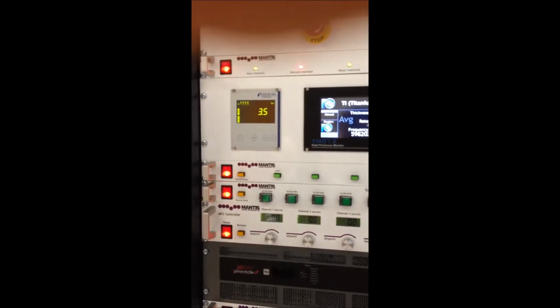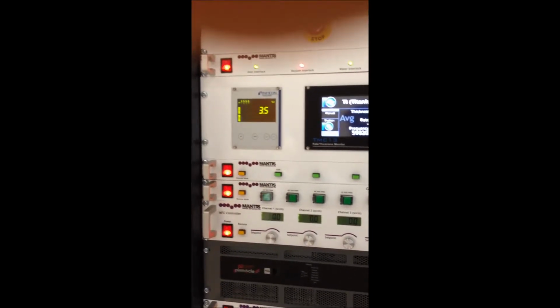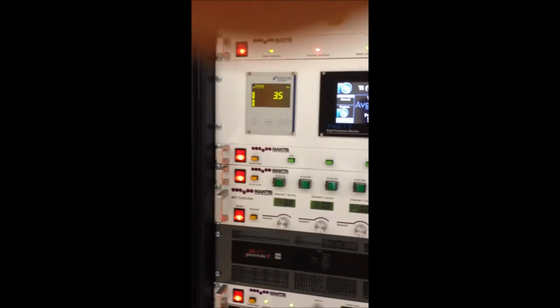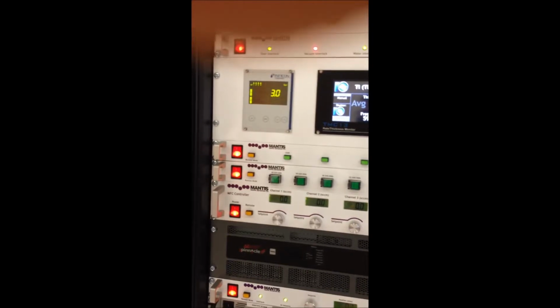Minus one for the turbo, okay? So whatever value, as long as it's better pressure than required for the turbo starting. So don't start it until you're at -1. Doesn't matter exactly, just as long as you're at -1 or -2. If I turn on the turbo now, will it go on? It will, yes. Just so you know, there's no automatic switch, no interlock for the turbo.